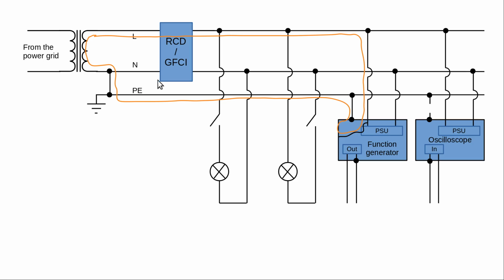This will mean that either the RCD will trip, because now there's substantial current flowing through live but not coming back through neutral, since it's going through the earthing wire instead, or the current might even be so high that the fuse or circuit breaker trips, which isn't drawn in here. But either way, something will shut off the power and give you a chance to remove the faulty device and correct the problem without any harm coming to you, the wiring, or the device.